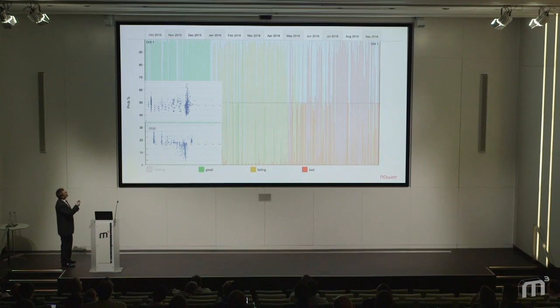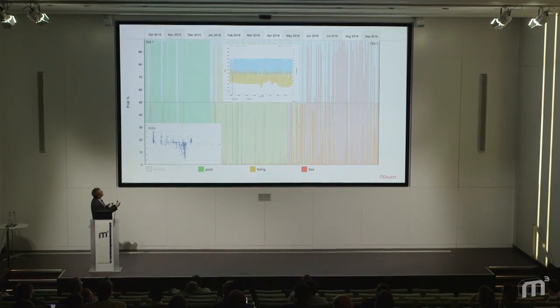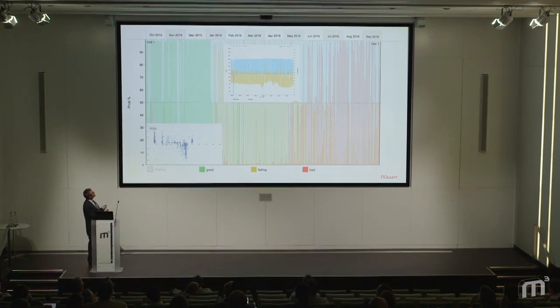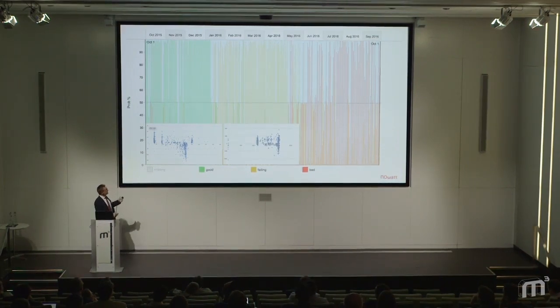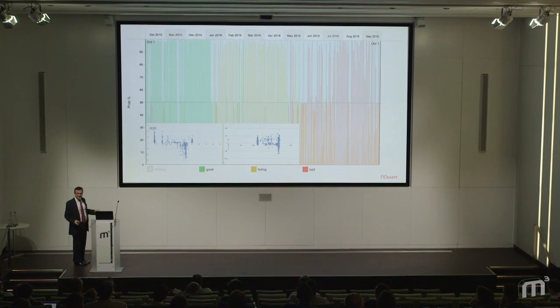Now, what's interesting is come January, which is an unusual time for a chiller to show a problem, the AI recognised something had changed. It saw a different pattern. And if we look at the raw data, we can see the condenser's now got a constant base load of around 1200 watts. And that probably means that the defrost heater has been permanently stuck on. Now, from the user perspective, there's nothing wrong. The condenser's going on and off with the temperature's cool. So this looks good. But if you look at the second order pattern, it was easy for the AI to see the change in condition. Between that and that, it was very obvious to see the difference.